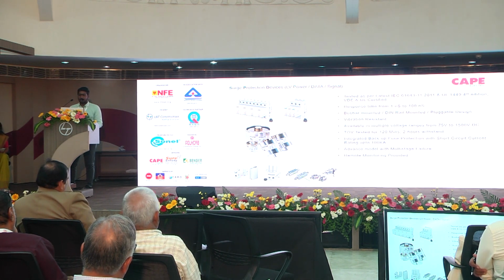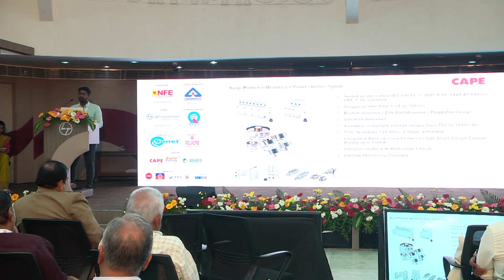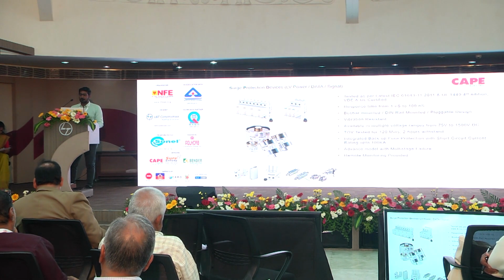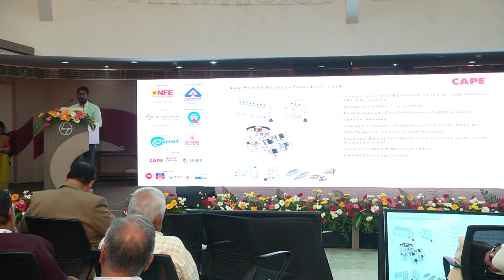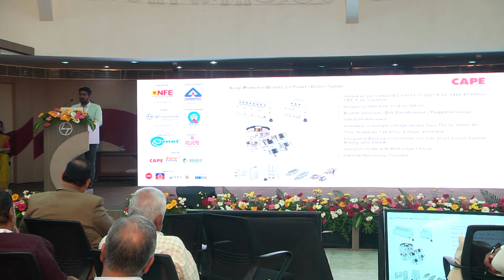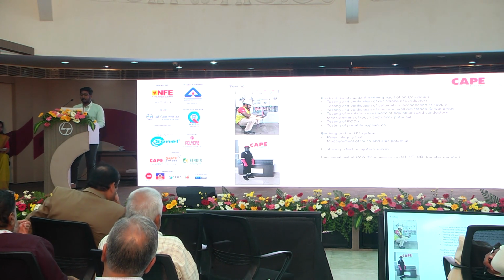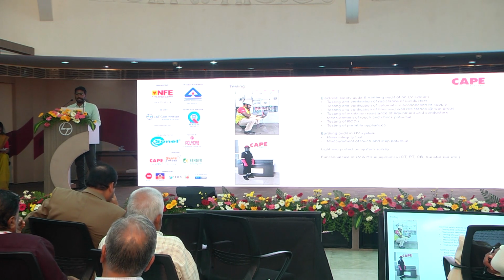And every SPD is temporary overvoltage tested for 120 minutes, and it is capable of withstanding 2 hours. It has an integrated backup fuse protection with short circuit current rating up to 100 kA. And we have an advanced model with multi-stage failure and remote monitoring provisions. And we also have a dedicated team for testing, and we completely look after electrical safety audit and earthing audit of an LV system.